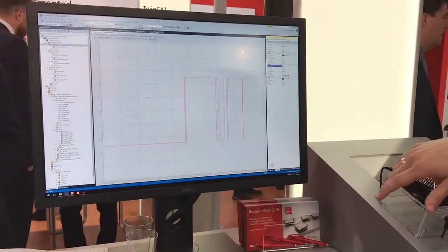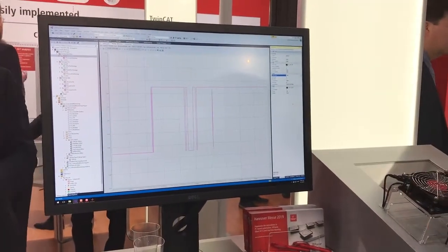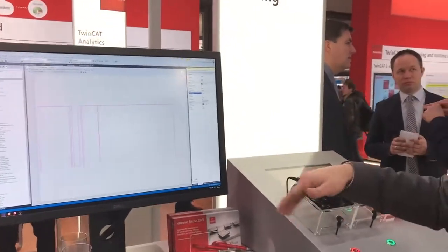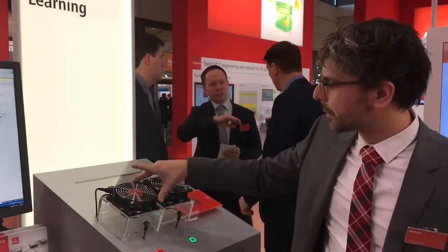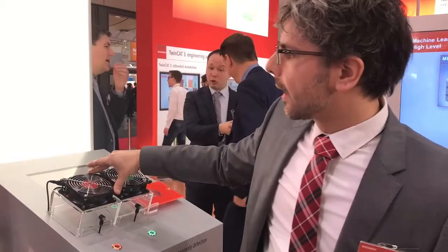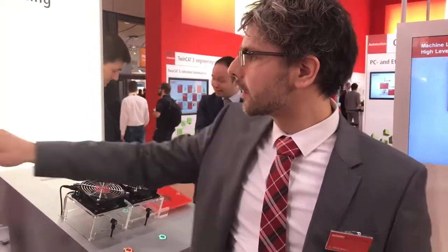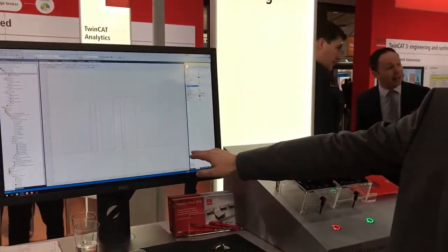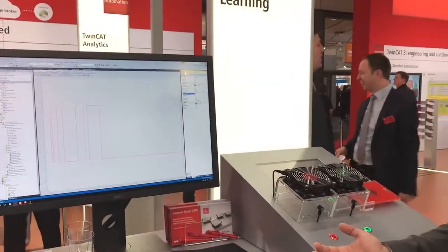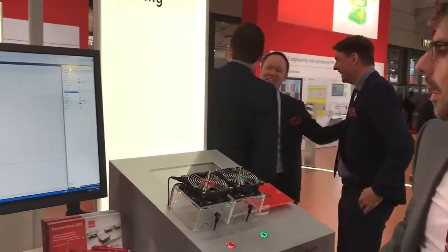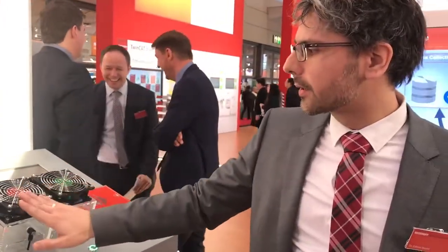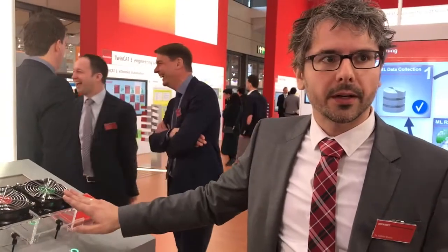Now the fan is turning off, and in this situation I have basically no information. Now the broken fan is starting, and once it's running, then the algorithm tells me, well, really something is wrong, something is different. Only in the area between turning the damaged fan on and the other fan on, there is some area where basically no information content is coming. There is a switch in between okay or non-okay.